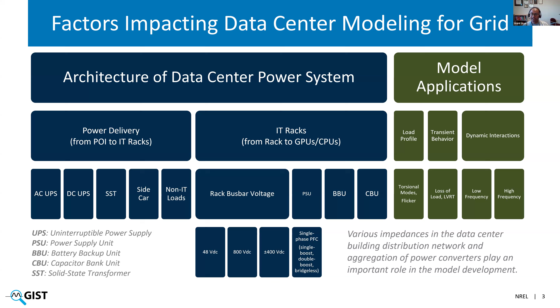On the IT rack side, what is there within the rack? Right now the industry is using 48 or 50 volt DC bus bar voltage for supplying these racks. But there's a lot of interest in new developments and real commercial technologies on 800 volt, plus minus 400 volt DC, again to fit a lot of GPU and compute power within a single IT rack. Depending on which bus voltage we use, the data center can look very different. Then there are PSUs that supply data centers with different topologies, and a few new technologies like BBU, battery backup unit, and CBU, capacitor bank unit, which I'll talk about soon. So let's start with architecture.